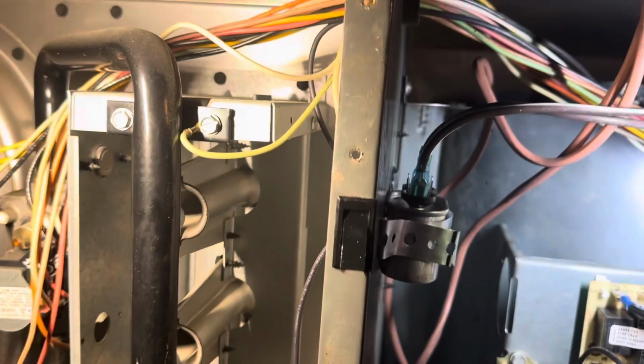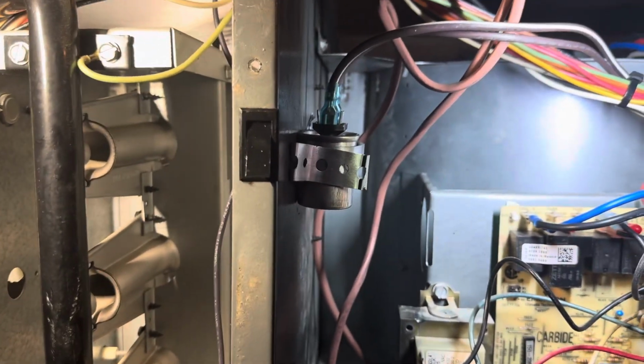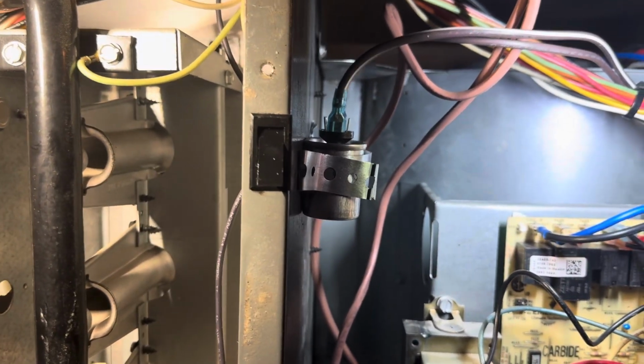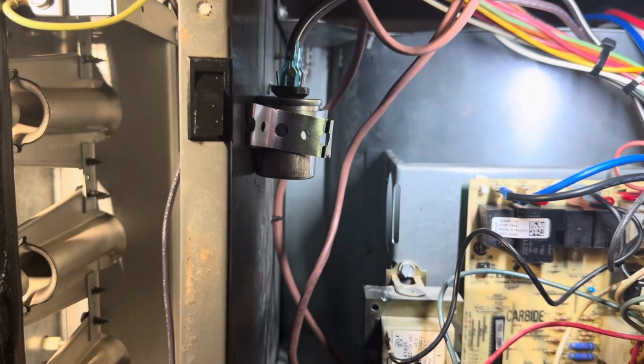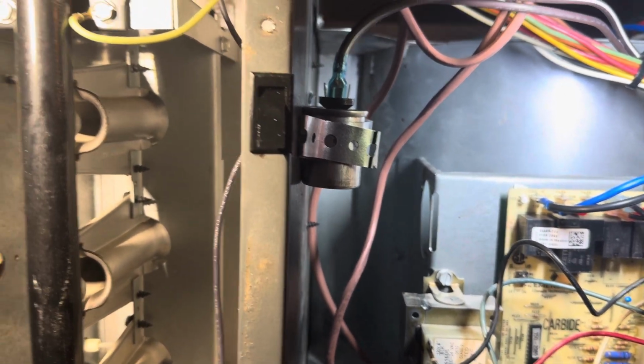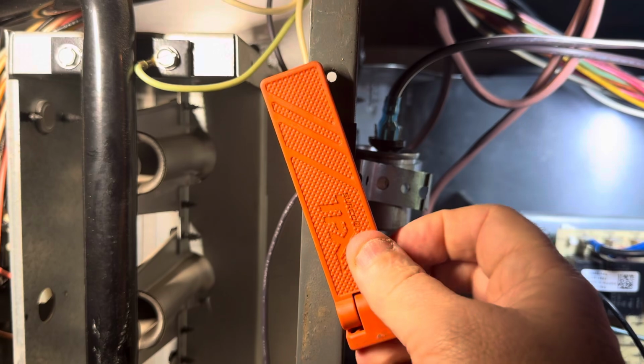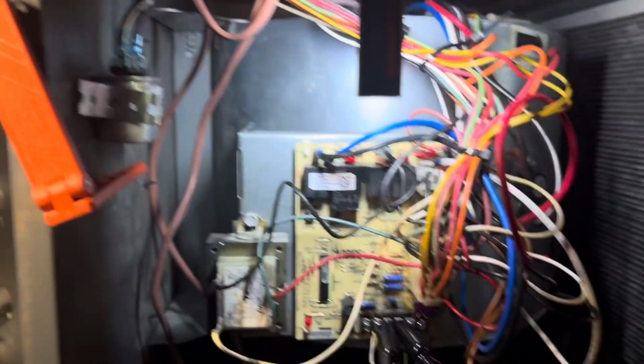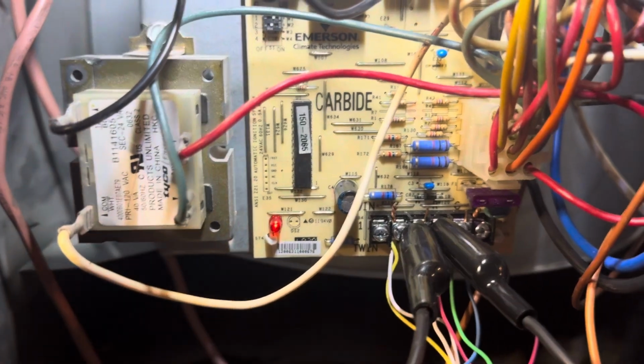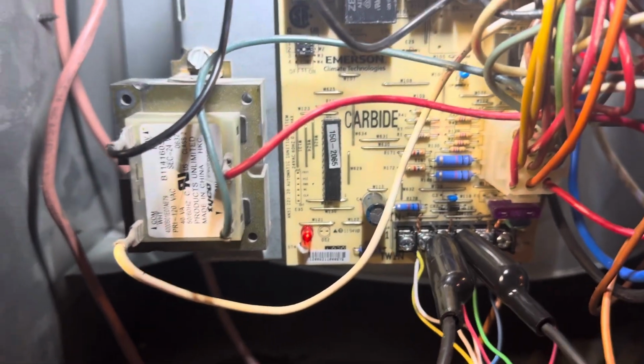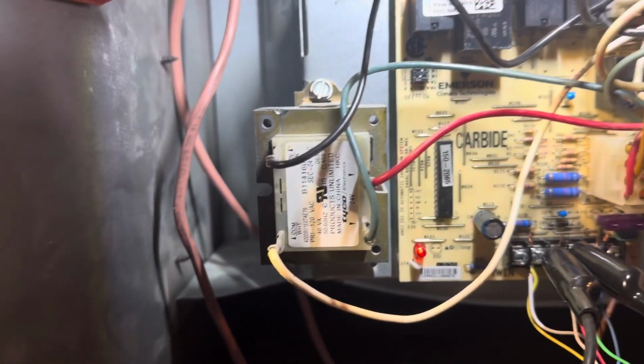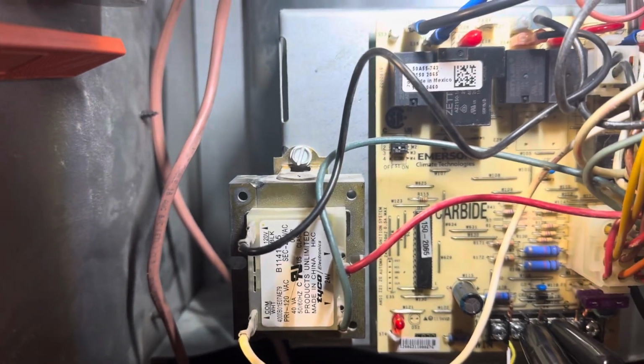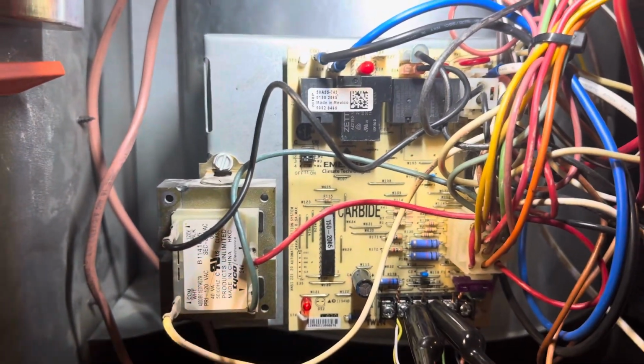Now let's connect up here our switch, and I have it wired up here. This is a safety switch on the door that I'm about to close, and we'll watch the sequence of operations here. Okay, so you should hear the click. We saw the light on the circuit board come on. If that doesn't come on, you could have a fuse here that's blown, or the transformer as well could be bad.